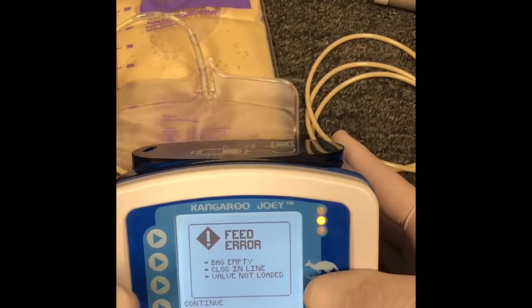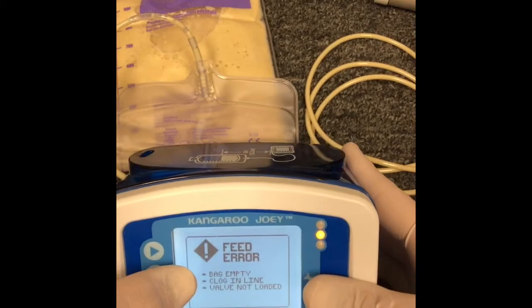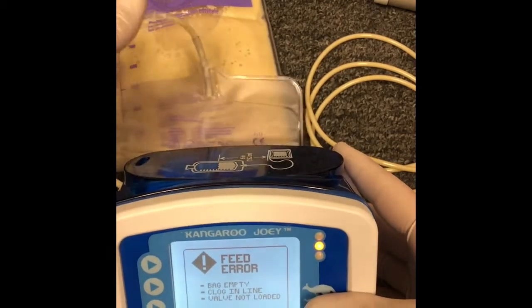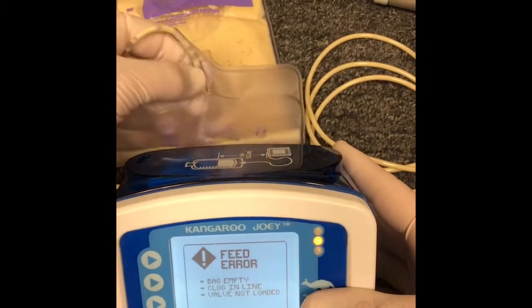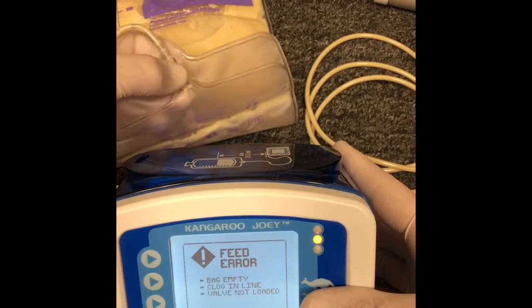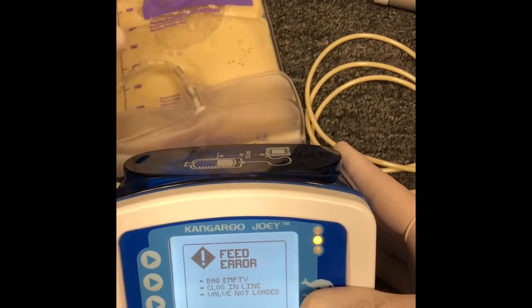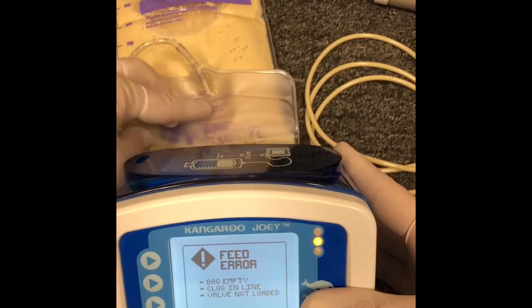So that's saying your bag is empty, there's a clog in the line, or your valve is not loaded. That's an issue between the bag and the pump, most likely caused by either no food or something clogging it up right here on this piece. It's hard to point and hold it, this piece.